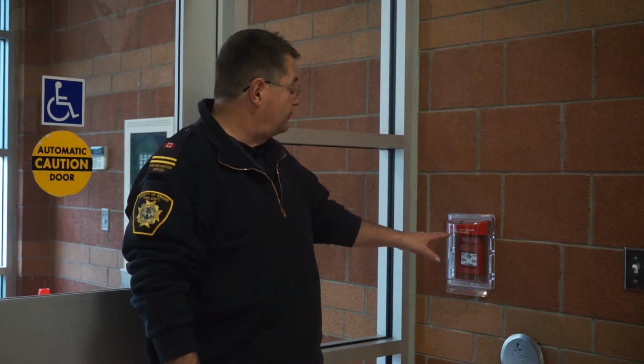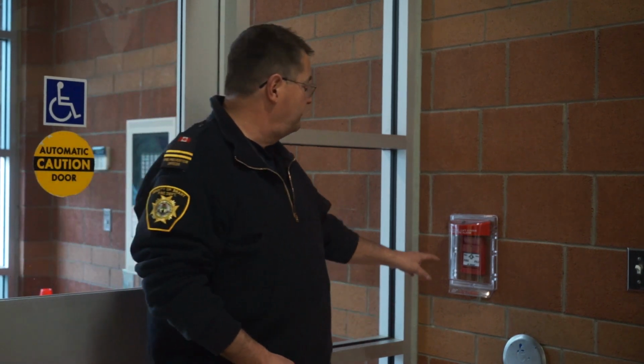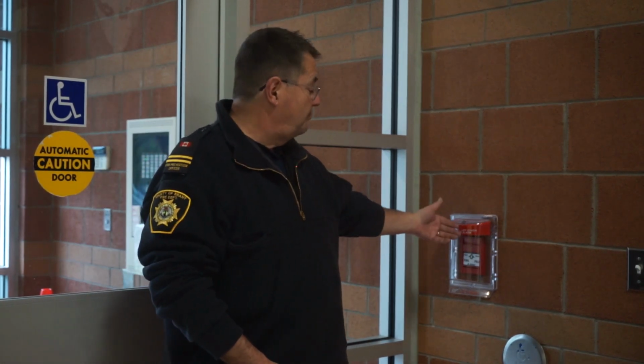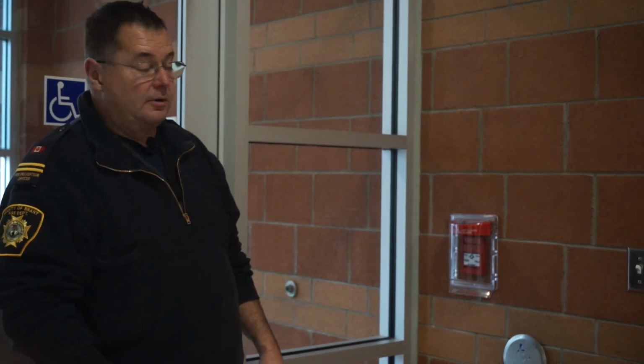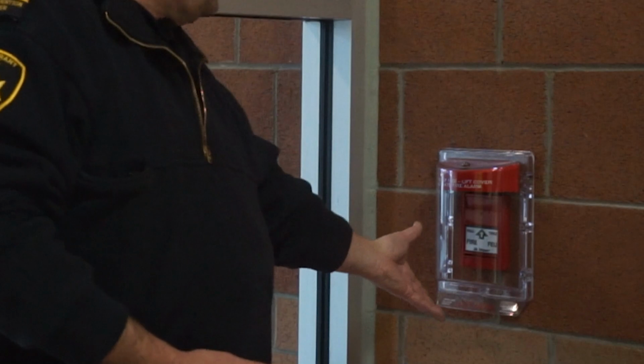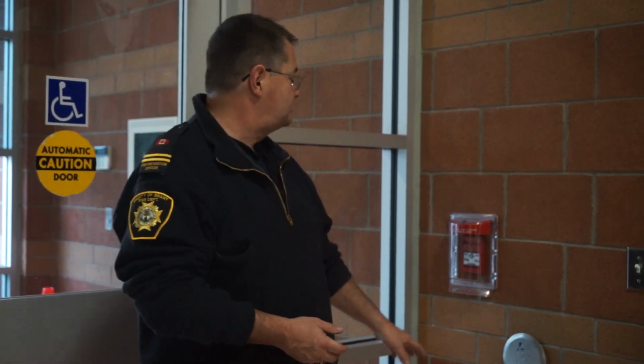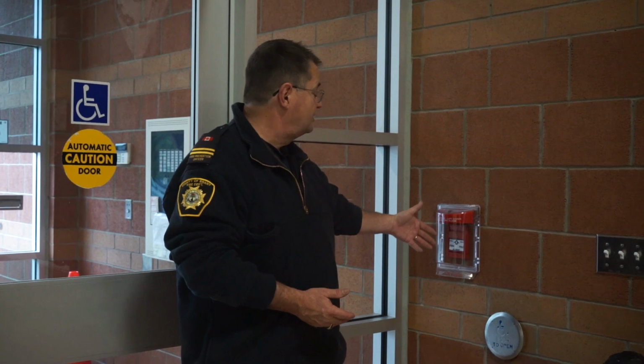pull stations, and for those of us that don't know, this is a switch that turns on the fire alarm system. So if we saw a fire or if we believed there was a fire, we physically activate this lever. By using this lever, we turn the fire alarm system on, and the fire alarm panel that we just looked at will set the bells and strobe lights into motion, and it will also call the fire department for assistance to this address. This cover plate has its own alarm, so if the teachers in the building hear a supplemental alarm go off, they know that somebody's lifted up the cover plate, and they need to come and make sure the students aren't getting us into trouble.